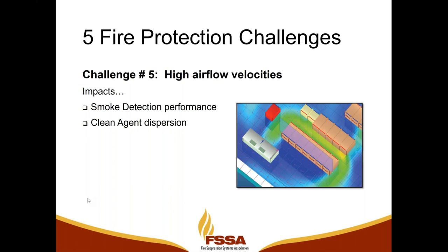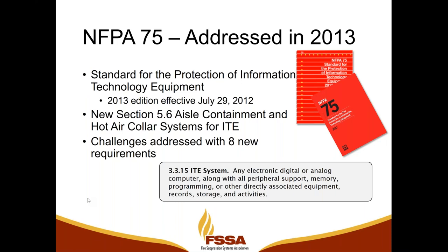Now, the good news is that in NFPA 75, the standard for protection of information technology equipment, which is an occupancy-specific standard for data centers, there is new information on how to deal with aisle containment. What we're going to talk about in NFPA 75 is mirrored in NFPA 76, the standard for the protection of telecommunications facilities. So 75 covers data centers, 76 covers telecom facilities, and we really see the same things happening from an aisle containment perspective. And so the requirements are the same in both documents.